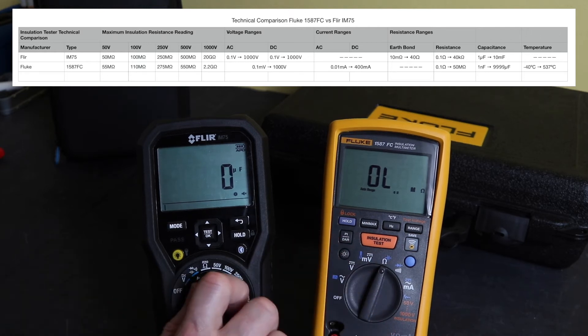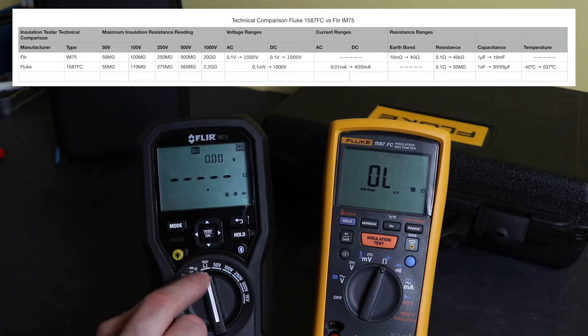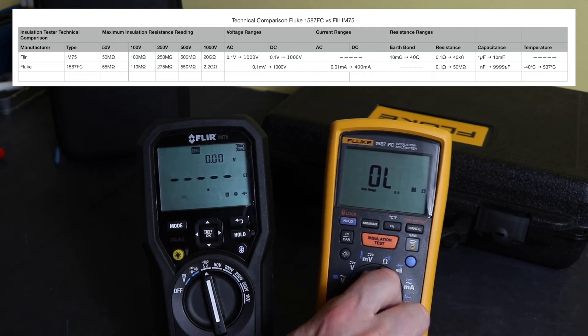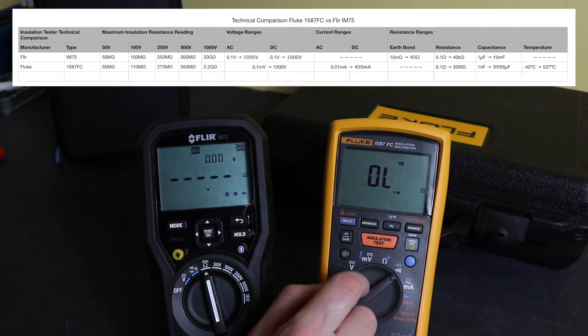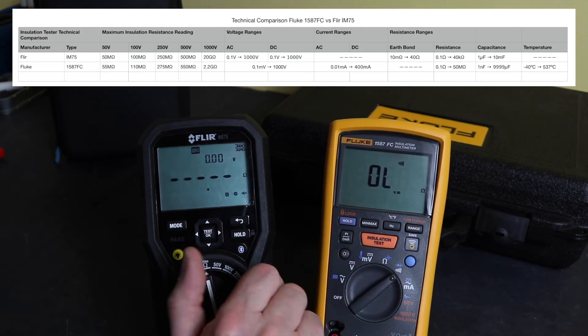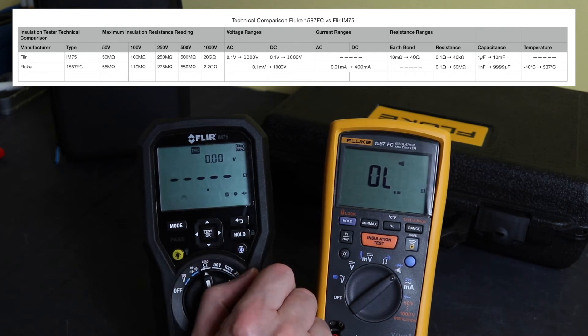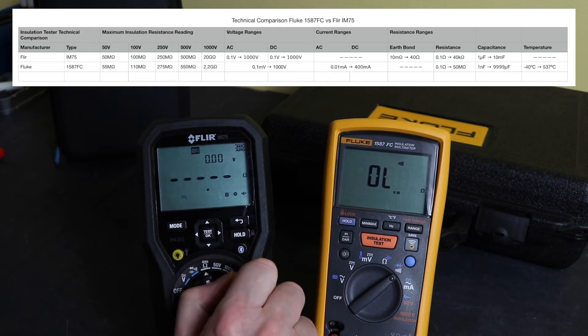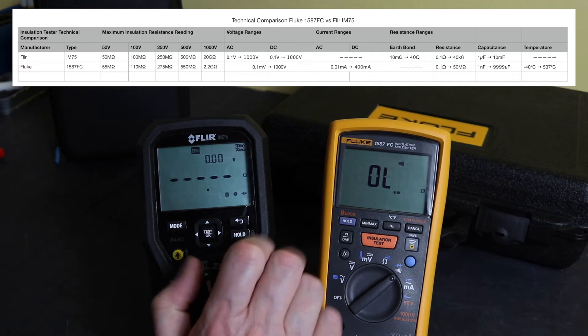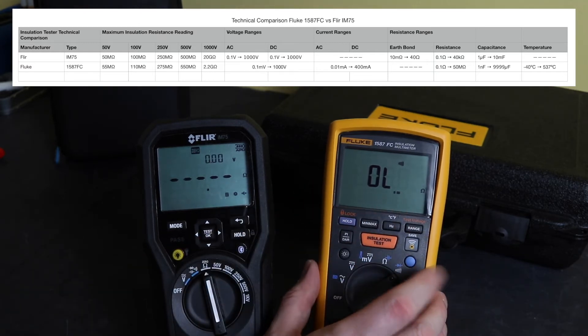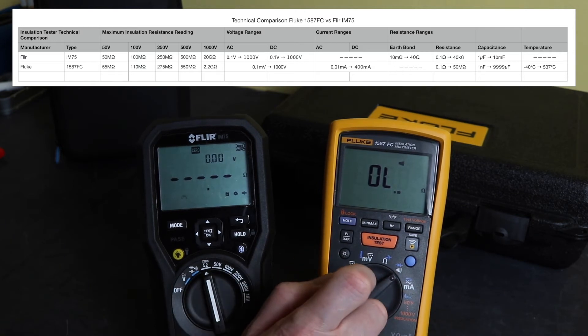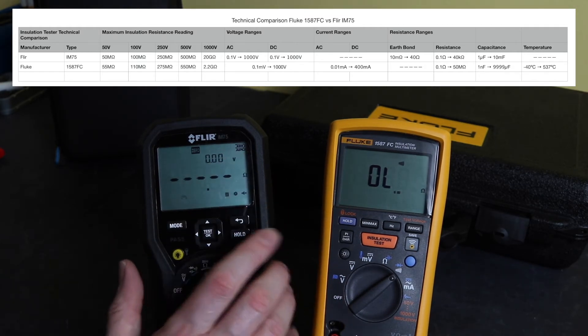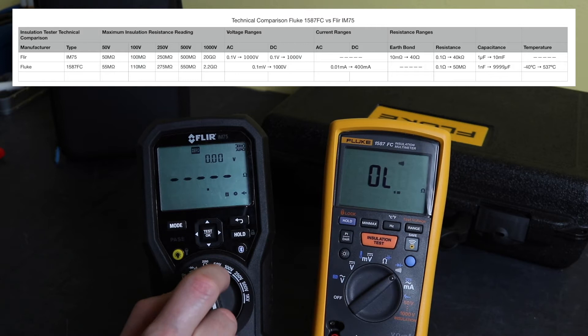Resistance-wise, you have to move around to the next position on the Flir. That's combined with the continuity function. Resistance is split on the 1587 and you flick it around to get continuity and diode onto the next one for the Fluke. Resistance range is 0.1 ohms to 50 megaohms, and for the Flir it's 0.1 ohms to 40 kiloohms. However, the Flir does have a 200 milliamp test function for measuring earth bond continuity, which is a requirement under the UK regs. Fluke does not have that facility, and so it loses out to the Flir on that occasion.